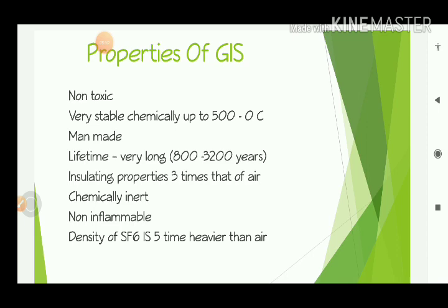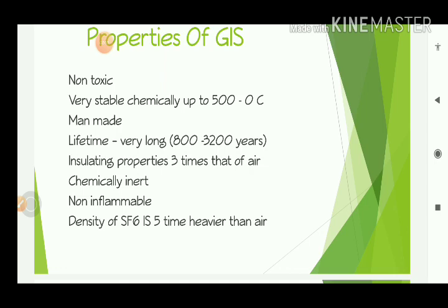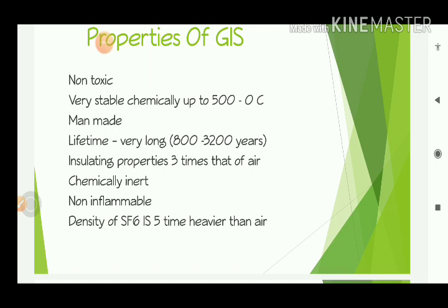The properties of SF6 gas: first, it is non-toxic — not harmful to human life. It is very stable chemically up to 500 degrees Celsius, meaning no chemical reaction occurs below that temperature. It is a man-made gas with a very long lifetime of 800 to 3,200 years. Its insulating property is three times that of air. It is an inert gas and non-inflammable — no fire hazard. The density of sulfur hexafluoride gas is five times heavier than air.